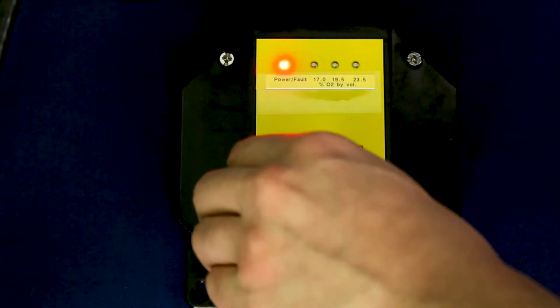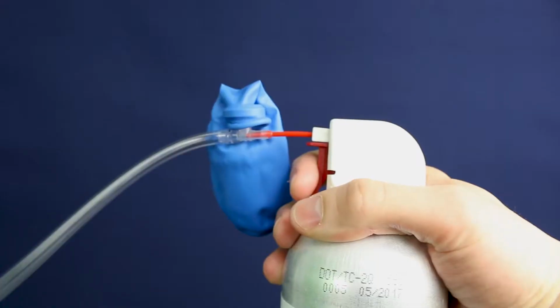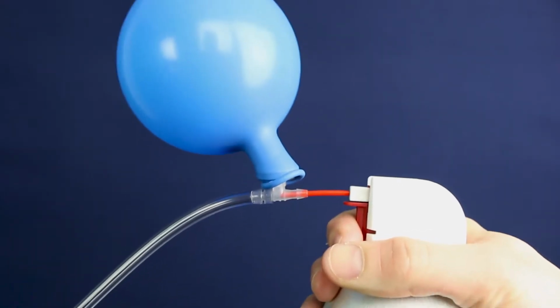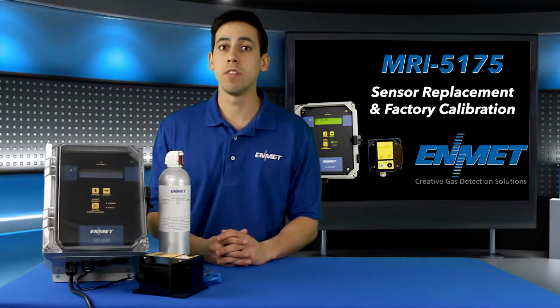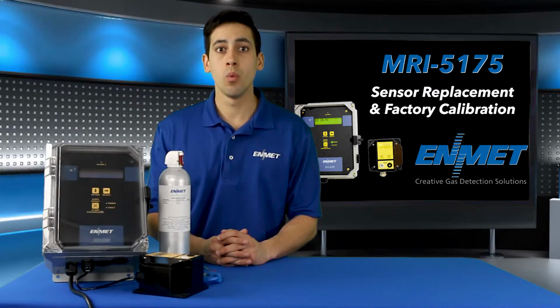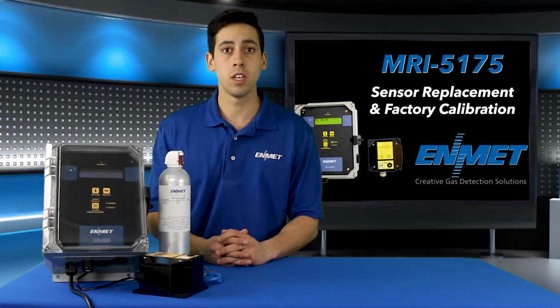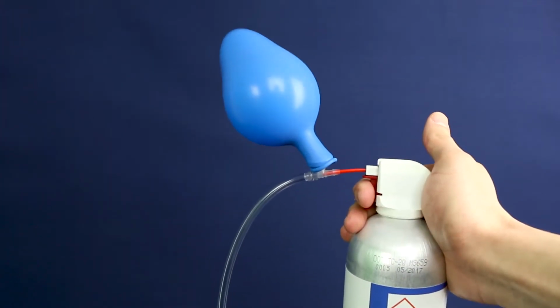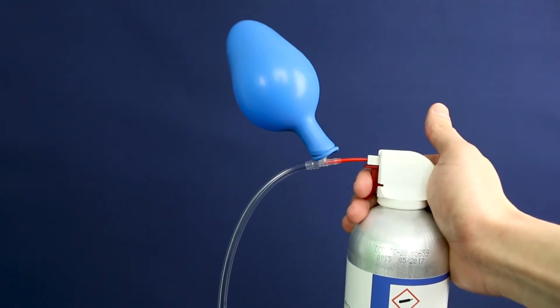Attach the MRI calibration adapter to the sensor and then pull the trigger on the cylinder and partially inflate the balloon. The MRI 5175 transmitter will begin to look for signal stabilization. This process will last from 60 to 120 seconds. Make sure to keep the balloon partially inflated during this time.